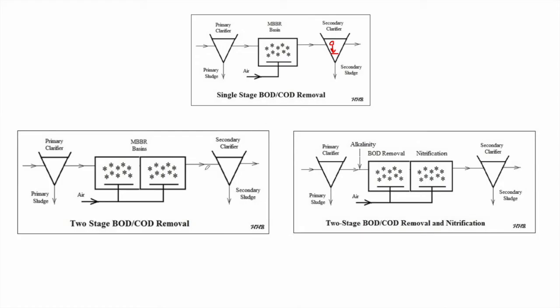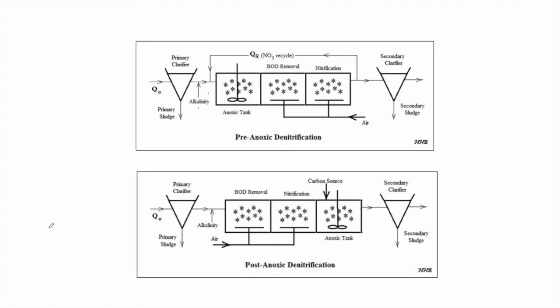In the single stage MBBR process we can only remove BOD and COD. For further removal, we can add another basin. If we also want a nitrification stage, we add a source of alkalinity before the BOD removal tank, and the second basin handles nitrification. Both basins operate under aerobic conditions.